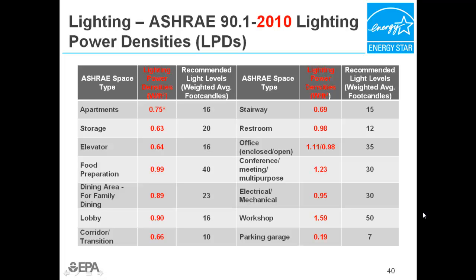Multiplying the lighting power density by the square footage of a given space type determines the ASHRAE allowance for that space. For example, a 1,000 square foot corridor would have a lighting allowance of 660 watts. Summing the allowances for all the common area spaces gives you the combined allowance. EPA will allow any individual space to exceed their lighting allowance as long as the sum of the installed lighting power for all the common spaces combined does not exceed the combined baseline allowance and illumination requirements are still being met.